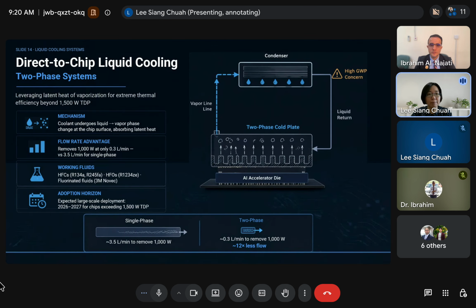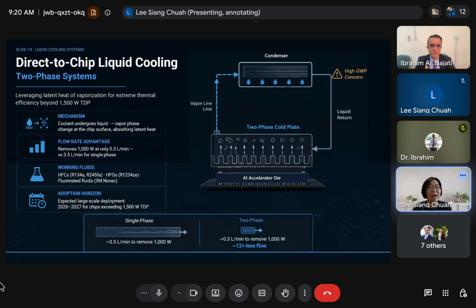Okay, two-phase cooling is a fundamental shift in thermal management and will define the next generation of artificial intelligence (AI) cooling. Unlike the single-phase system, the coolant in two-phase cooling boils at the surface, undergoing a liquid-to-vapor phase change. This leverages the latent heat of vaporization, which allows a much higher heat removal efficiency. The impact is significant. To remove 1,000 watts, a single-phase system may need about 3.5 liters per minute of flow. So we can see that two-phase cooling achieves higher performance by using the fluid itself as the heat transport mechanism.